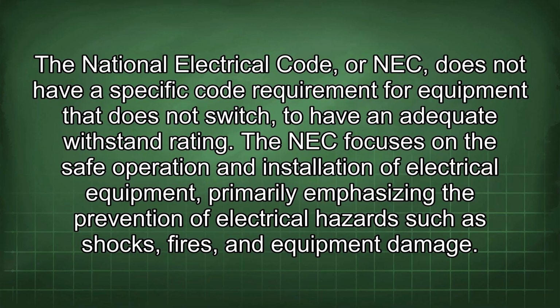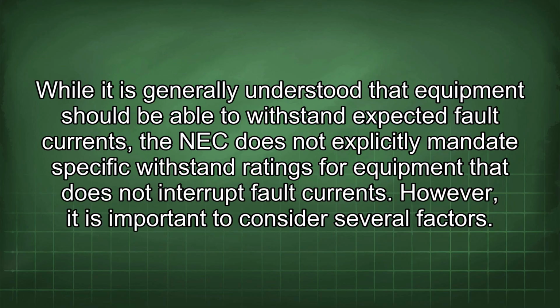The National Electrical Code, or NEC, does not have a specific code requirement for equipment that does not switch to have an adequate withstand rating. The NEC focuses on the safe operation and installation of electrical equipment, primarily emphasizing the prevention of electrical hazards such as shocks, fires, and equipment damage. While it is generally understood that the equipment should be able to withstand expected fault currents, the NEC does not explicitly mandate specific withstand ratings for equipment that does not interrupt fault currents.